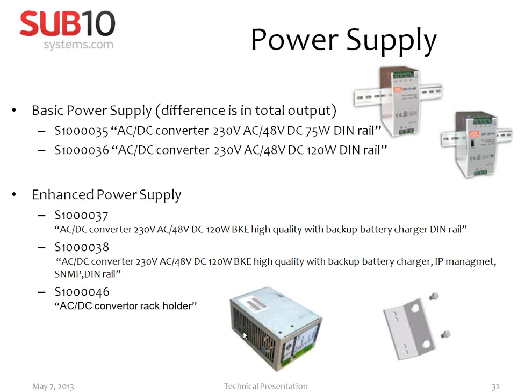This is useful for high critical applications, or if the customer needs high redundancy and a more reliable solution, because in case of trouble with the power supply, you get this information before you see any drop on the link. For example, if AC input goes down, you see it immediately from the power supply, and the battery can hold the link running for a couple of minutes or hours, based on battery size.